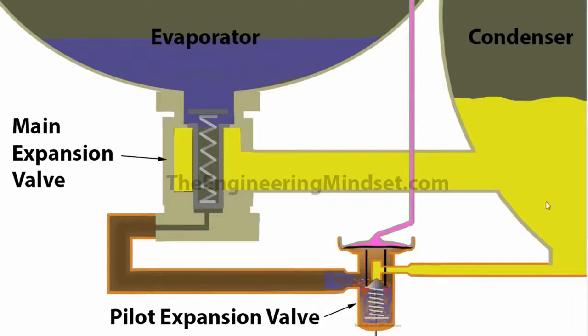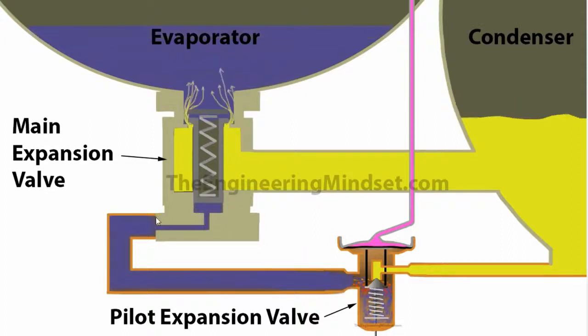So the refrigerant is starting to flow from the condenser through here and into the pilot valve, and then that is going to start to flow through into the liquid line. As that refrigerant starts to fill the liquid line, it starts to build up some pressure and starts pushing against this piston housing here. That pressure is going to lift the piston off its seat, and that's going to allow the main refrigerant in the condenser to start to flow through this valve.